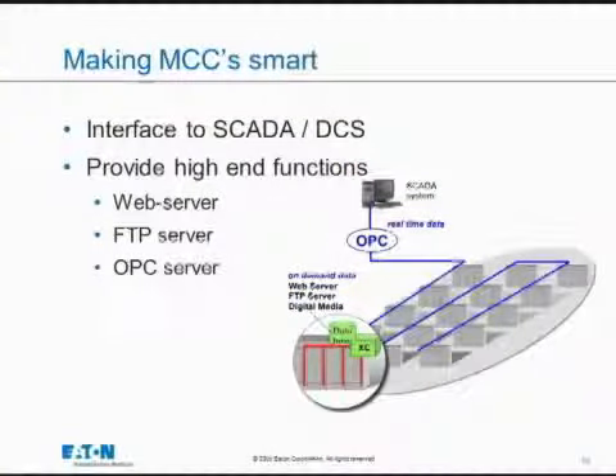It also provides high-end functions like web server, FTP servers, OPC servers, which basically allow you easy ways to access the information. So when we were looking at the screens there and you wanted to basically see what was going on, well, they're inherently web-enabled, which means that you can dial in from any web access point and see exactly what is going on the screen itself. Consequently, if you want to get information, let's say of what the logging information is, you can download that through the FTP server. And if you want to tie it directly to a SCADA package without using a standard field bus, you have the ability to do that through the OPC server.